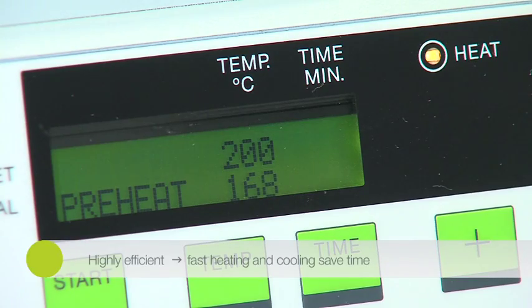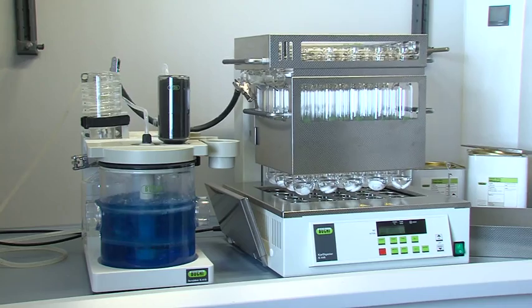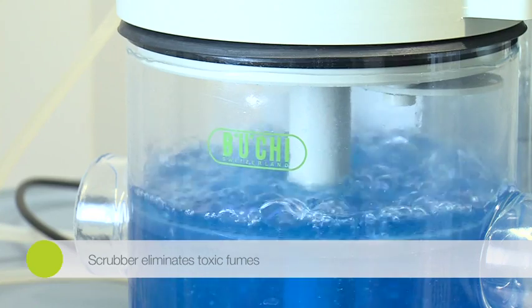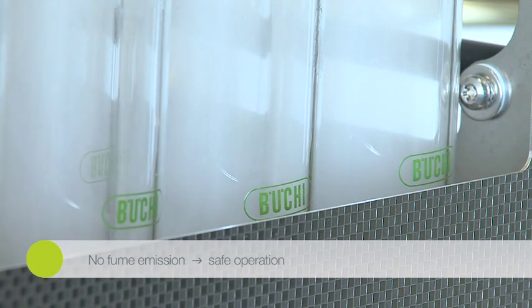Highest sample throughput is achieved as the total time needed for digestion is significantly reduced due to the short heat-up and cool-down periods. The Büchi Digester K-449 includes fully automated programming, a convenient automatic lift for lowering and raising the sample tube rack, and full control of the scrubber.